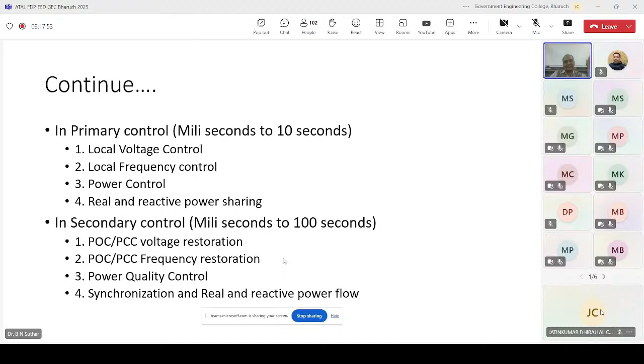The third one is the tertiary control. Tertiary control sits on top of primary and secondary control, and it requires proper data, forecasting and planning. It does the work of supervision and scheduling, deciding how much power will be taken from which generating plant or RES, and whether power needs to be drawn from the grid or supplied to the grid. This tertiary controller is responsible for these operations.